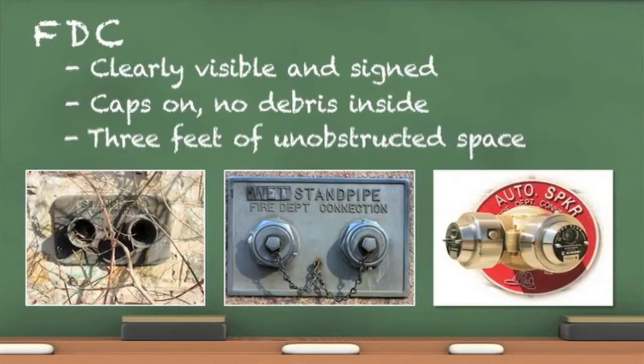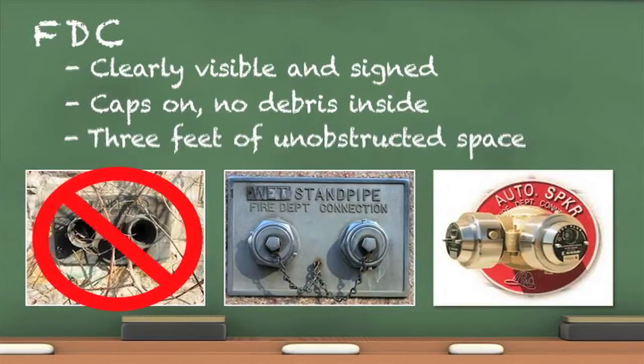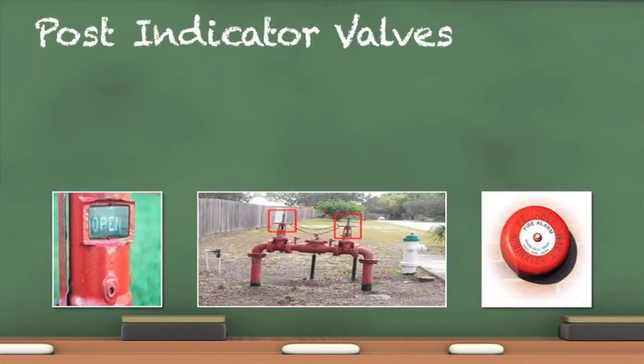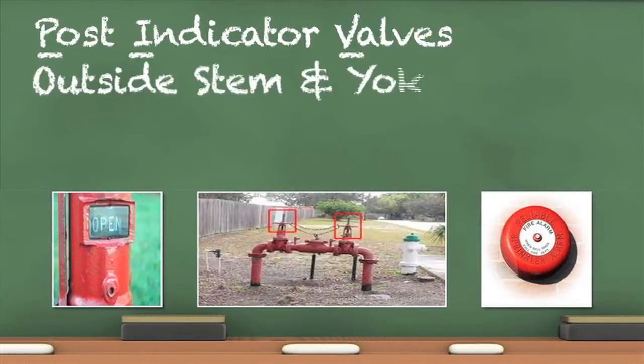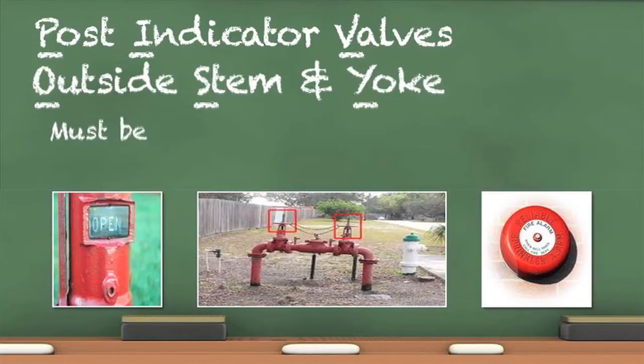The photo on the left shows an obstructed FDC missing its caps. Post indicator valves and outside stem and yoke are indicators that tell if the valve controlling the flow of water to the sprinkler system is open or closed. They must be locked in the open position.